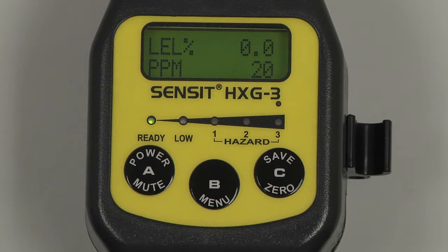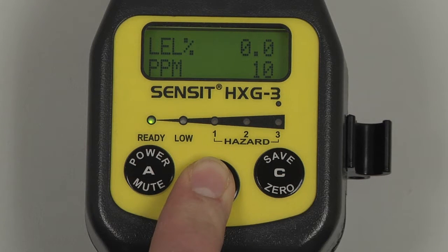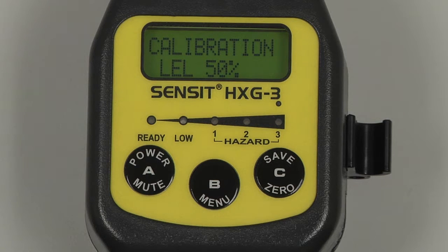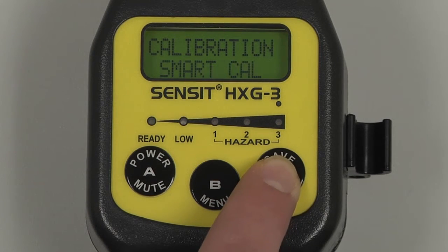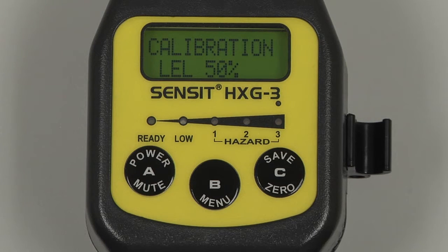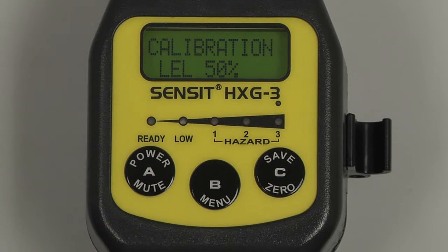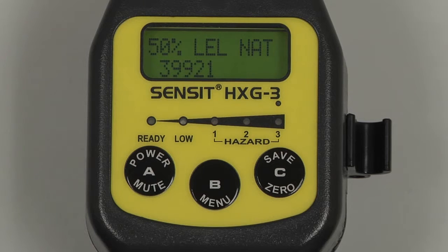Allow the instrument to warm up for an additional 5-10 minutes before calibrating. To begin, enter into the user menu by pressing and holding the B button, and scroll through the menu by pressing and releasing the C button until Calibration appears. Select by pressing and releasing the B button, and we will have a menu for the different possible calibration points. In this case, we only have 50% LEL methane, because that is how the instrument is set up. So we can attach the regulator to the calibration gas, turn on the regulator, and attach the cal adapter to the inlet at the end of the gooseneck. Select by pressing and releasing the B button, and the calibration process will begin.